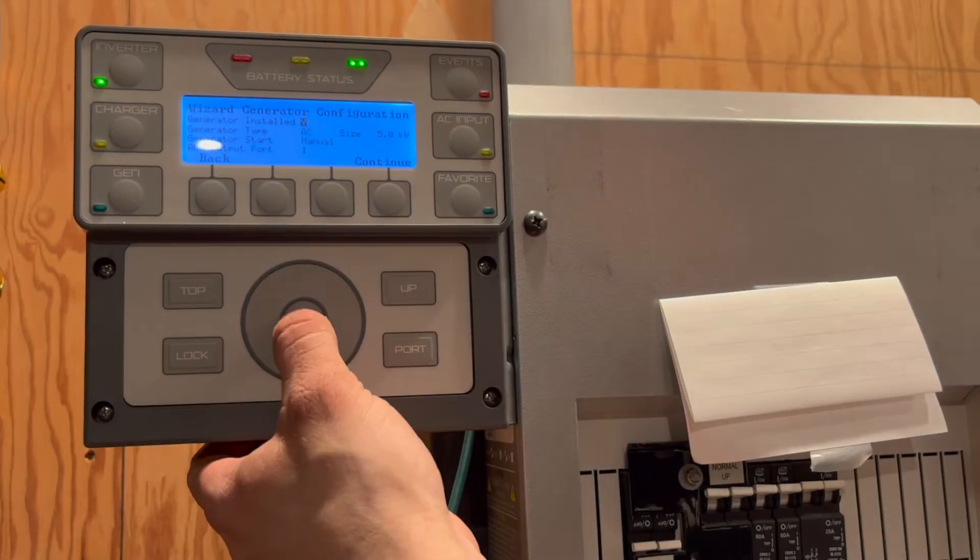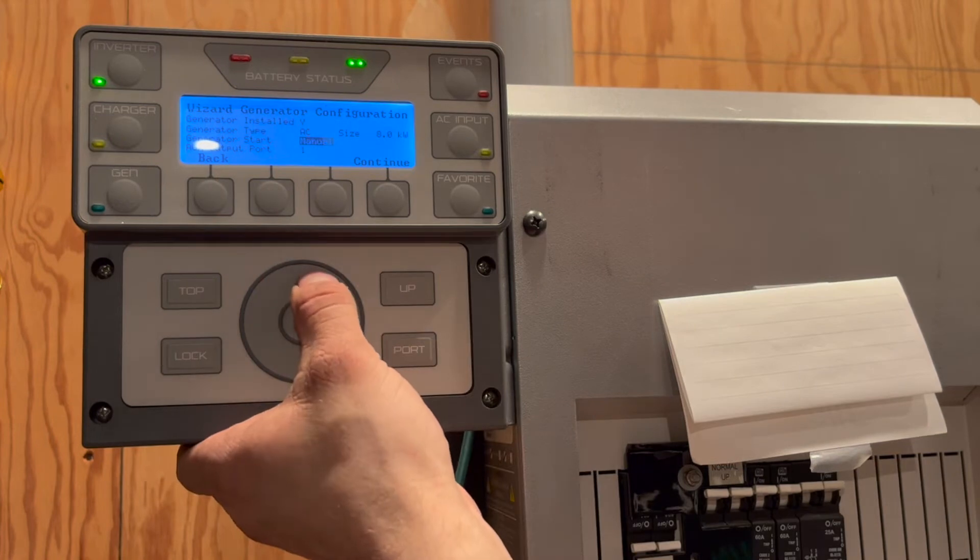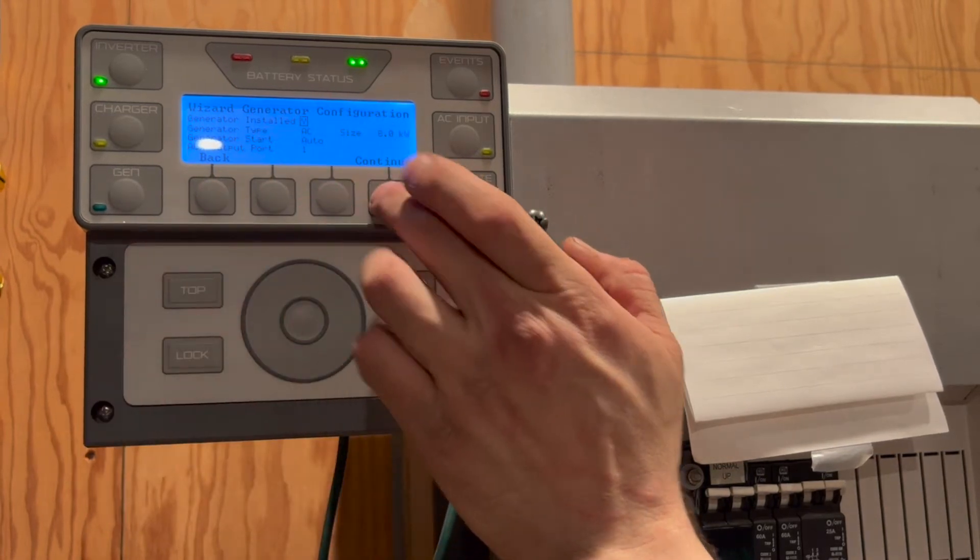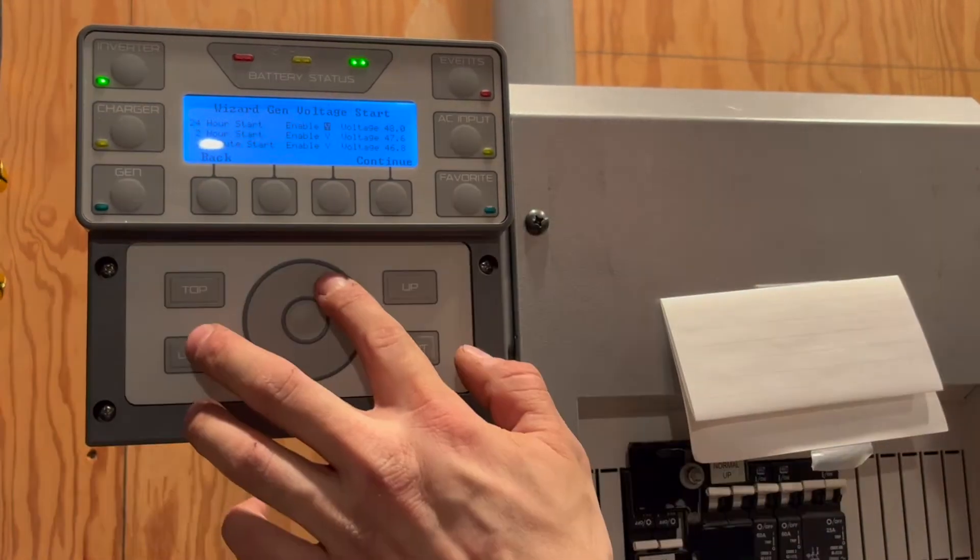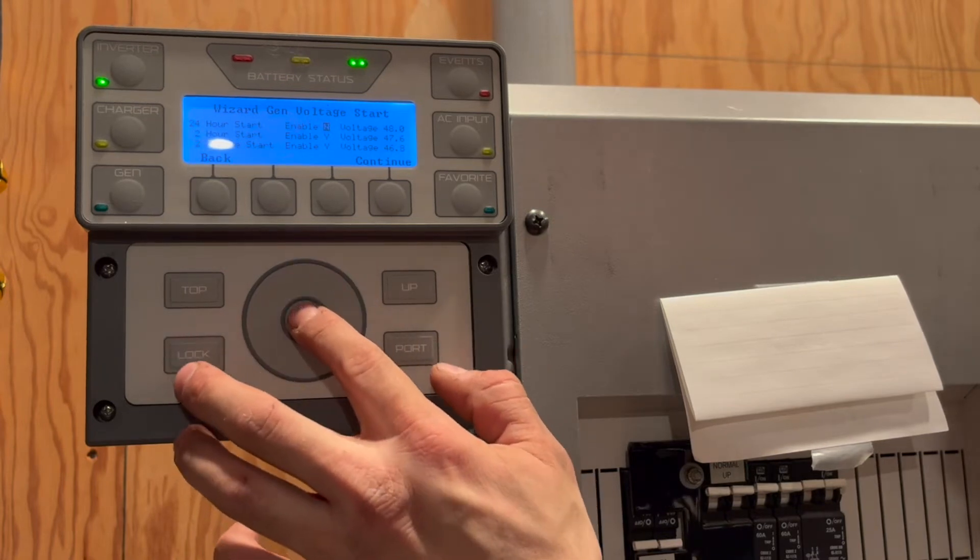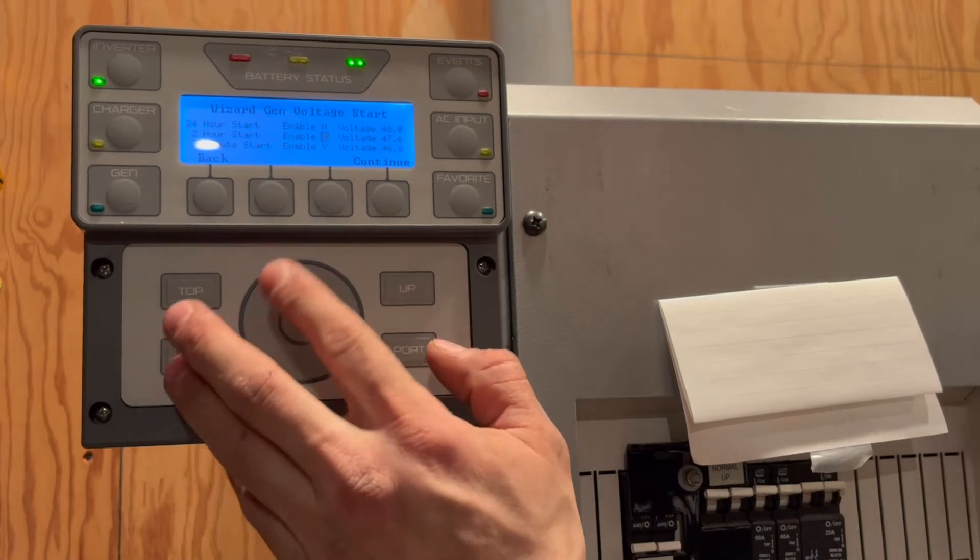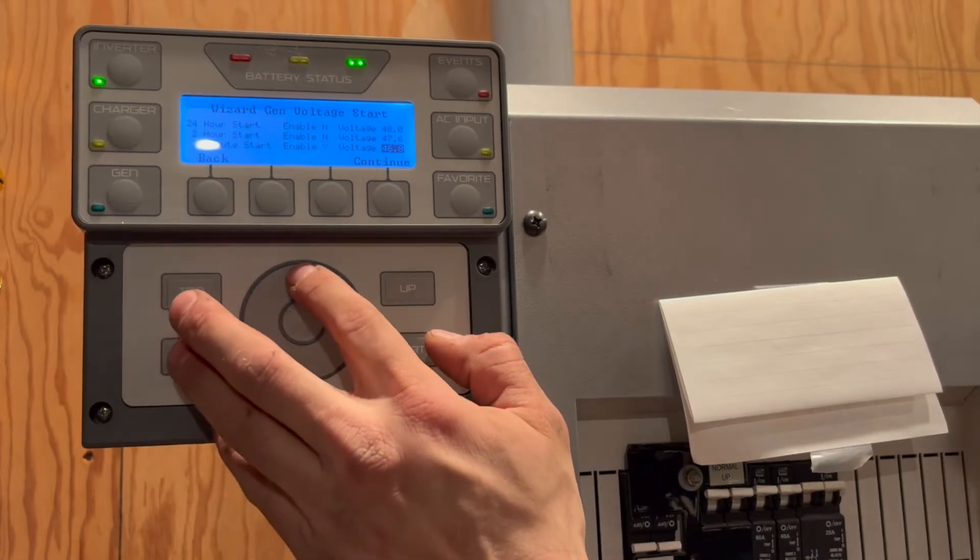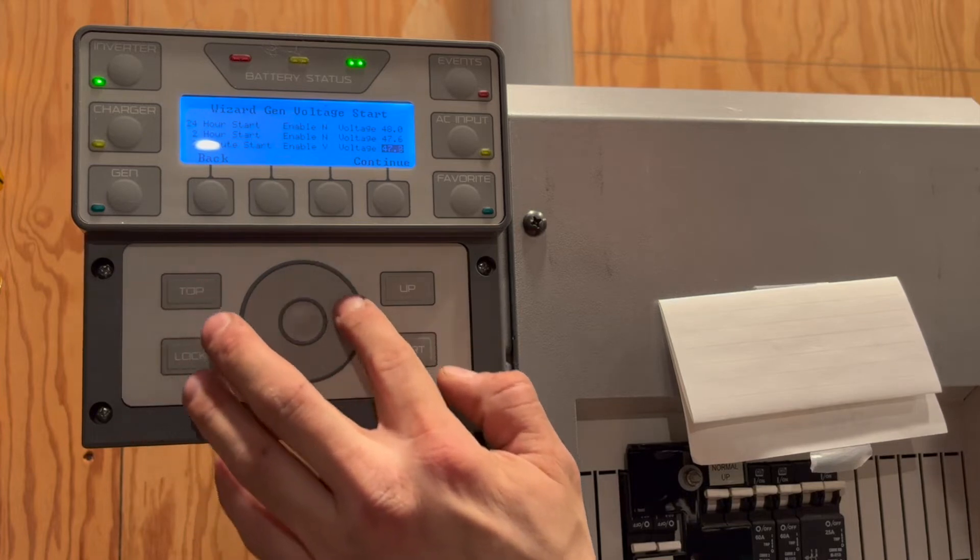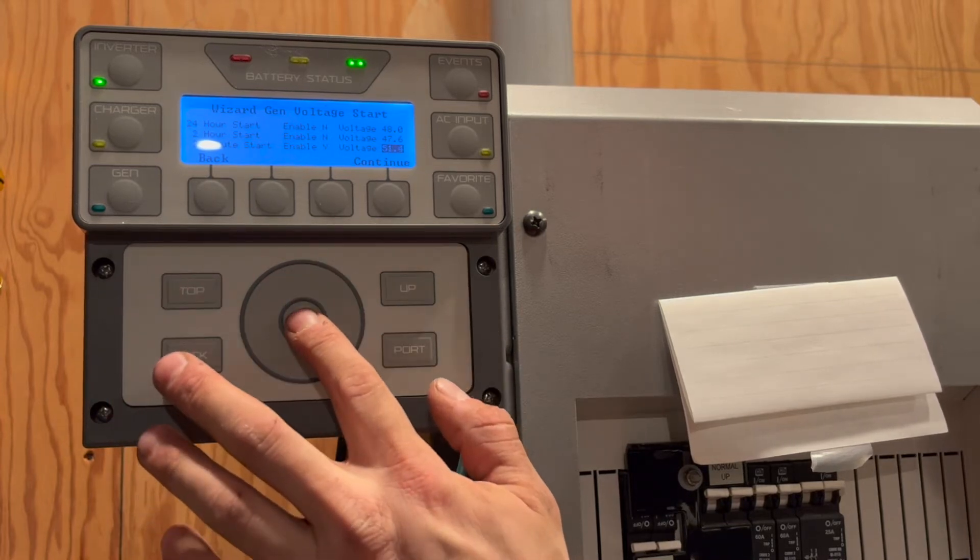We will set the Mate to auto, and then it will trigger a relay to start the generator when the batteries reach the programmed voltage. We are only going to use the 2 minute start voltage, and in this case it will be set to 51.4 volts, which should correlate to roughly 80% depth of discharge.